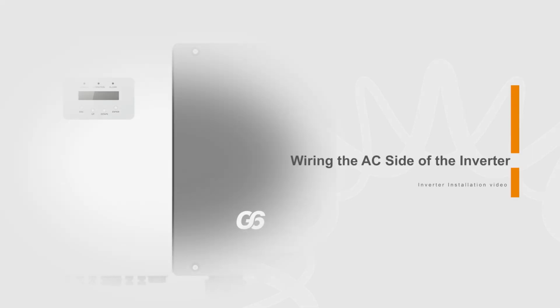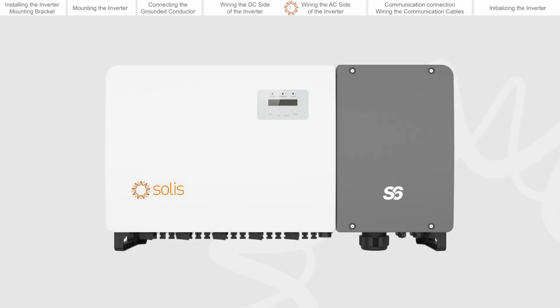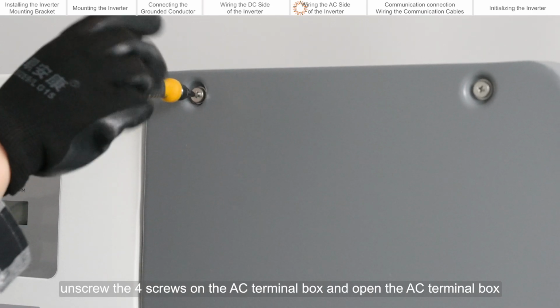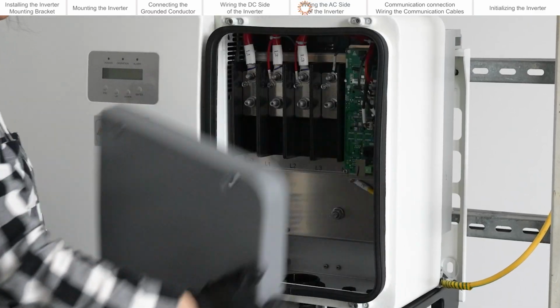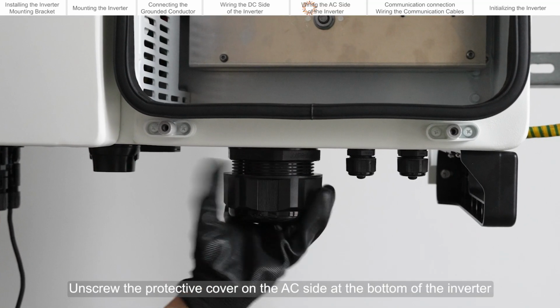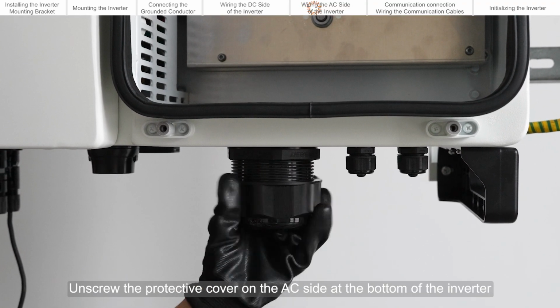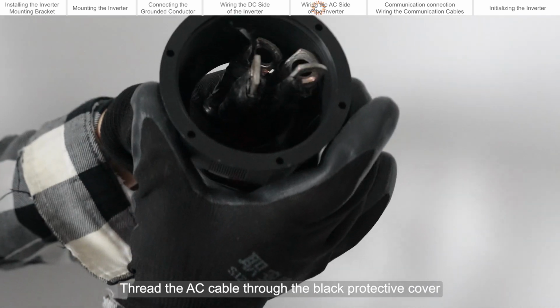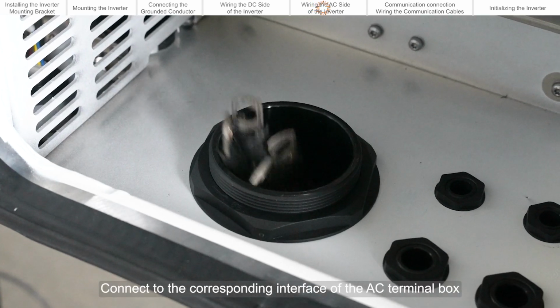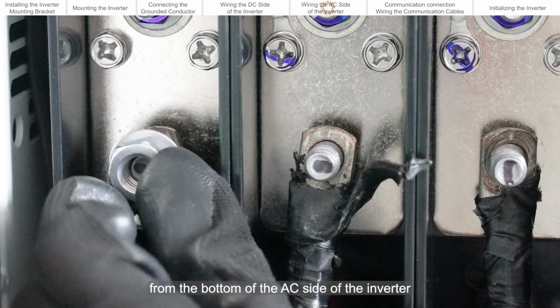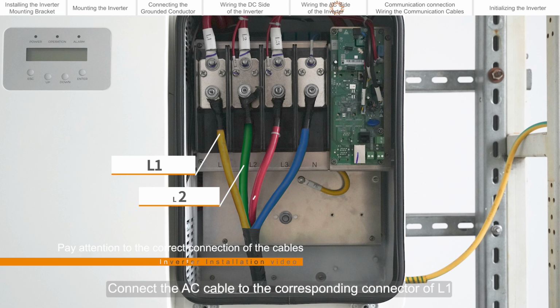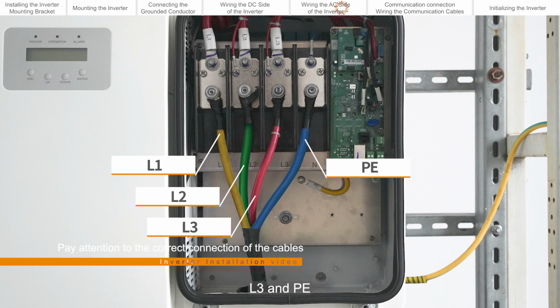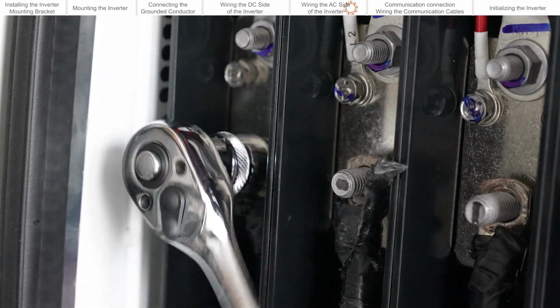Wiring the AC side of the inverter. Before connecting the AC cable, unscrew the 4 screws on the AC terminal box. Unscrew the protective cover on the AC side at the bottom of the inverter. Thread the AC cable through the black protective cover. Connect to the corresponding interface of the AC terminal box from the bottom of the AC side of the inverter. Connect the AC cable to the corresponding connectors of L1, L2, L3; the PE wire can be excluded. Tighten the nut using a socket.